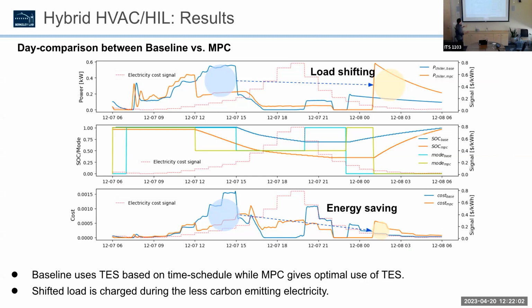Basically what the MPC is doing here on the orange line is knowing that it can predict the thermal load ahead of time, it actually decides to discharge the thermal energy storage earlier than when the price signal hits compared to the baseline. So what happens is now all of a sudden you have to charge more overnight, but it knows that the price signal is low there, so it doesn't matter. It'll charge overnight a little more to then discharge earlier every time.